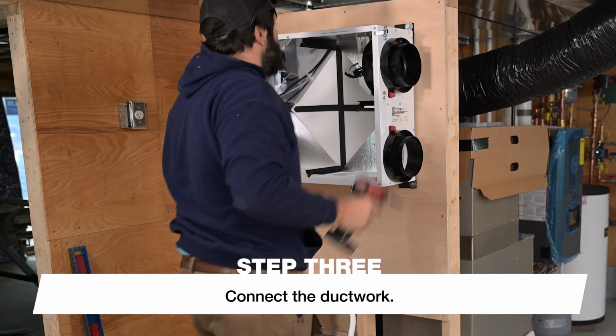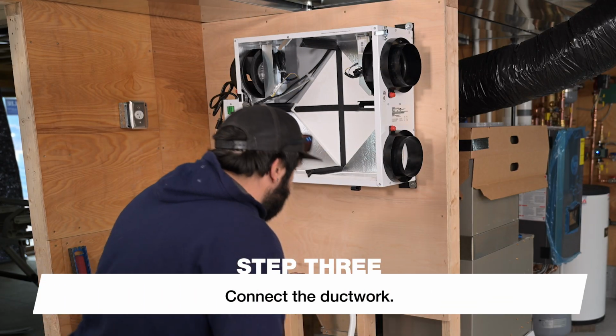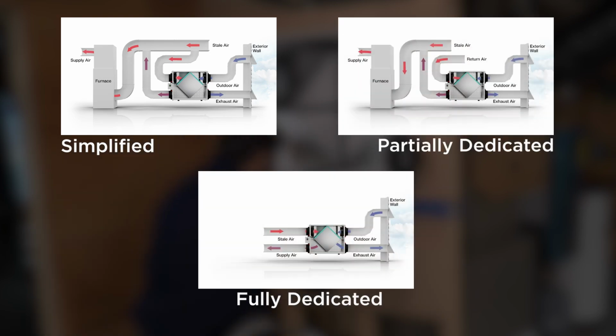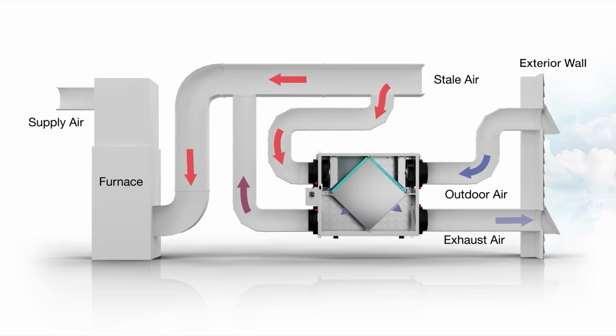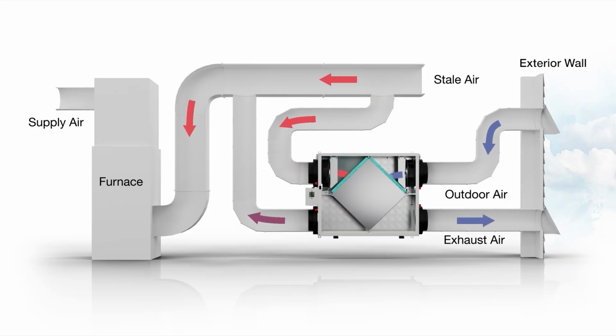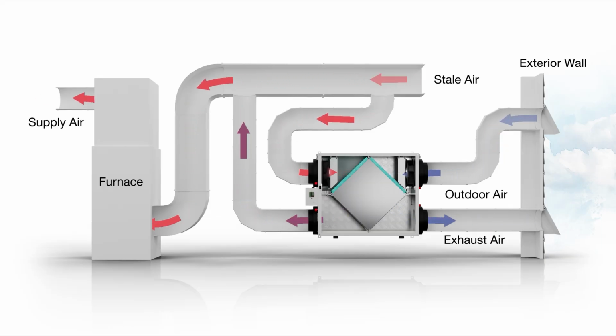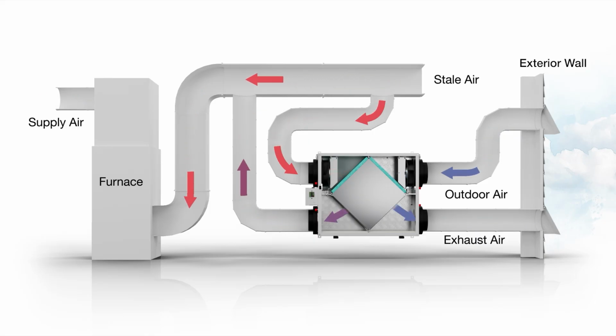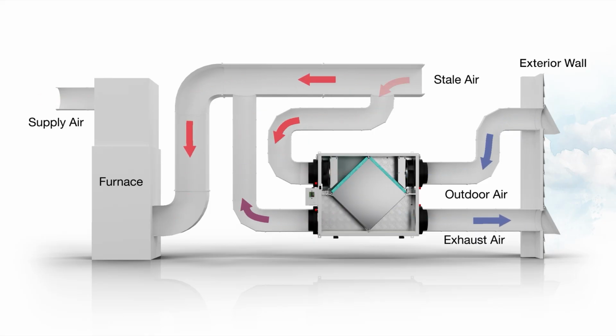Now you'll connect the ductwork. There are three main types of installation configurations: simplified, partially dedicated, and fully dedicated. In this example, we are showing a simplified installation where the ERV connects directly to the air handler's cold air return. Stale air is drawn from the cold air return duct, and fresh air is introduced downstream into the same duct.